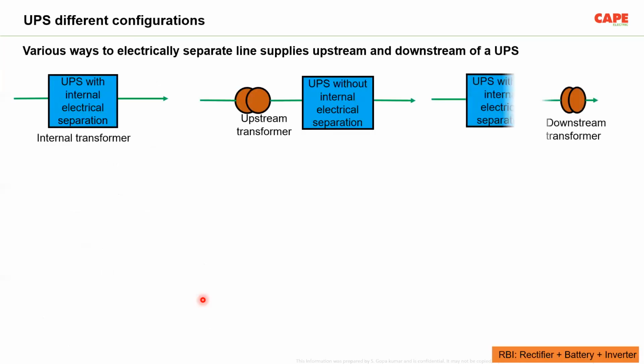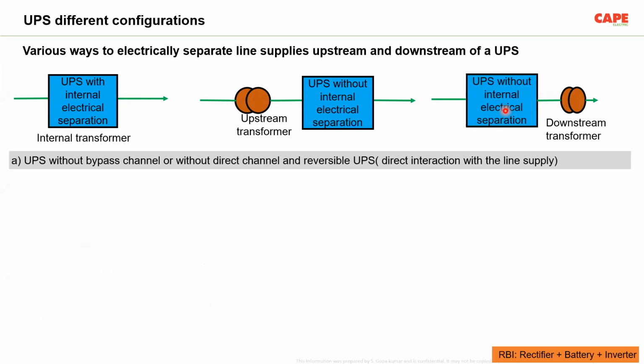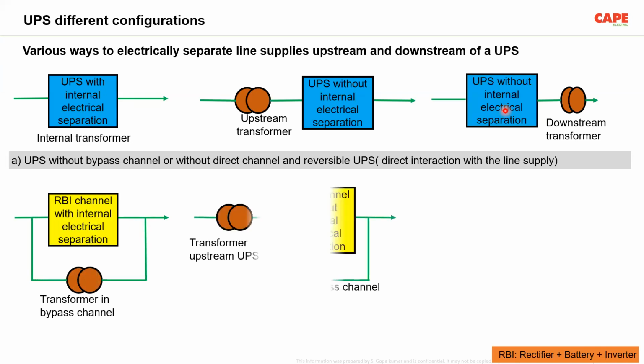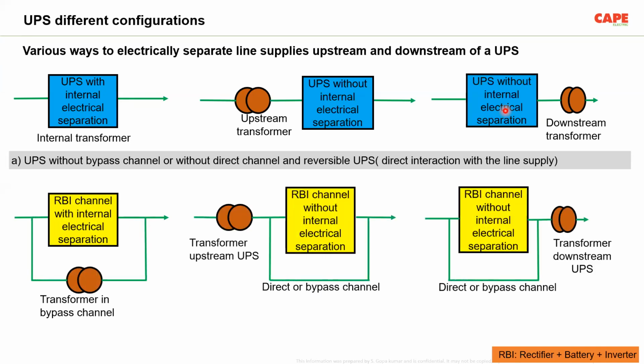Now, the recommended ways of using UPS. If you have a UPS with internal electrical separation, you can use the UPS for your single phase load. If your UPS is without electrical separation, that means there is no internal isolation transformer, then we are supposed to use an isolation transformer either at the input of the UPS or at the output, something like this, which is shown in the figure. And this is a UPS without a bypass channel, without the direct channel and reversible UPS. And if you have a UPS with a bypass channel, this is the way we are supposed to use it.